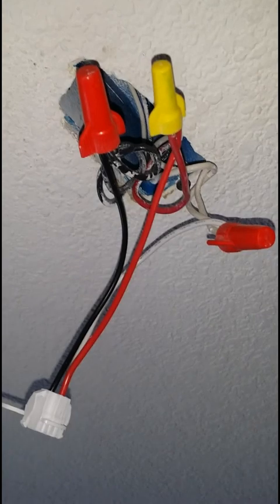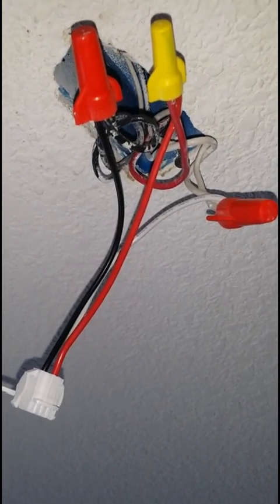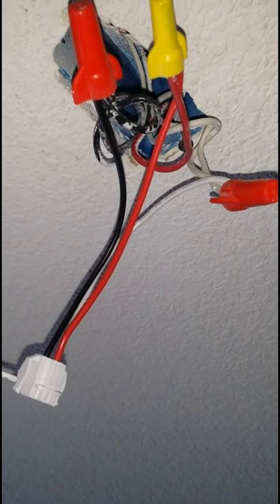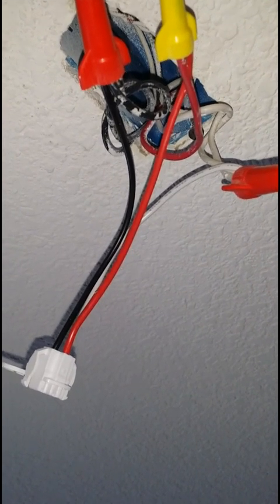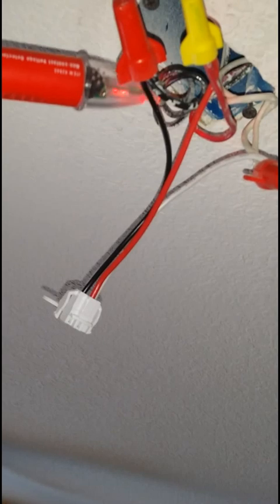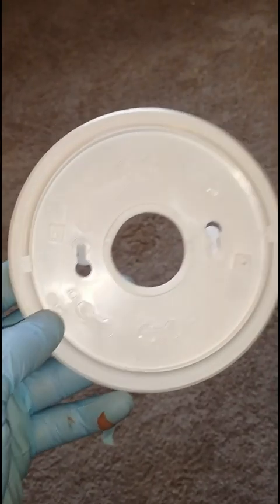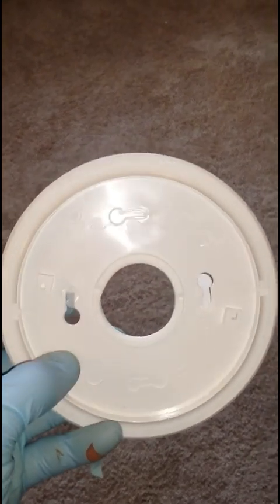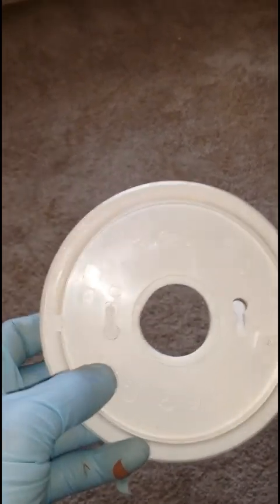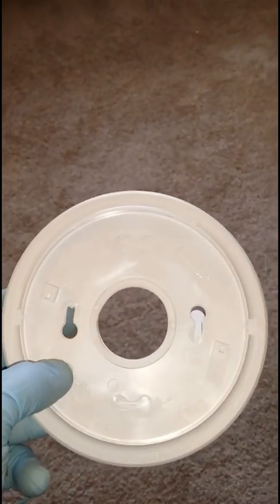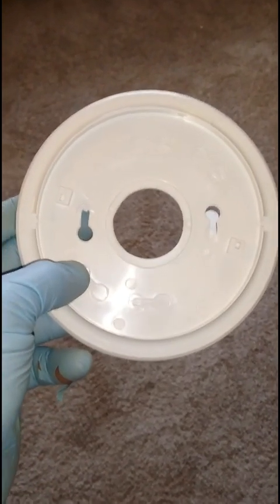What you'll do is go back to your circuit breaker, turn the circuit breaker on, and we're going to test to see if there's voltage going through this smoke detector harness. Turned it on. So we do see here that we do have voltage going down. You don't want to test it up here because there's going to be power coming through the line. You want to test it down here and make sure that the voltage is being detected at the base of the harness. Now we're going to attach our new base. The holes may be preset already, or you may have to use a screwdriver and pop them out. So just make sure that you do that before you go on the ladder and put your base on.